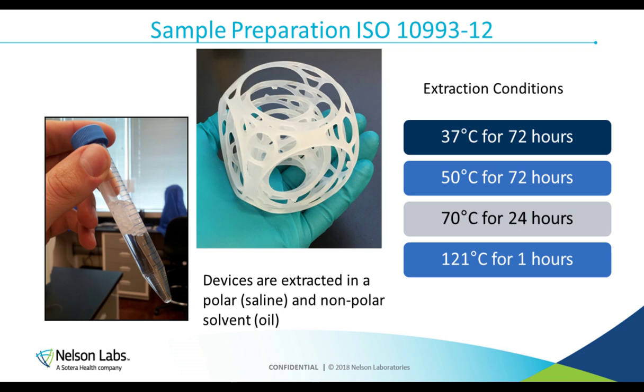And then the extraction conditions are the ones that are allowed in 10993 Part 12 for irritation testing. The most favored extraction condition is the 50 degrees for 72 hours. If you lower that temperature to 37 degrees, there needs to be justification for that. And the reason here is that we want to see an exaggerated extraction. So 37 degrees seems logical because that's basal body temperature. However, we just want to do a little bit of worst case escalation and make the test as sensitive as we can. So that's why we typically choose the 50 degrees for 72 hours.